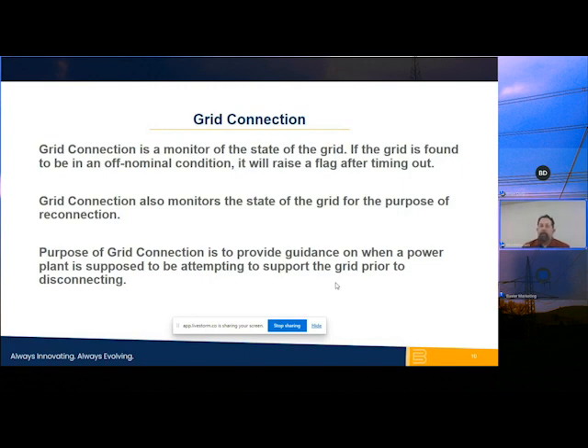If we have a problem and we disconnect from the utility grid, we're also going to monitor the state of the grid after the disconnect, for the purpose of reconnecting, because we also want to continue to support it when the grid's back to normal, and we want to continue to make sure that grid is safe and reliable. And the overall purpose of these grid connection codes is to provide guidance on when a power plant or a power source is supposed to be attempting to support the grid or disconnecting from the grid.